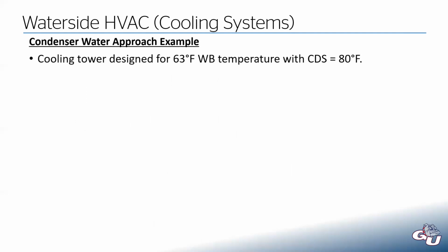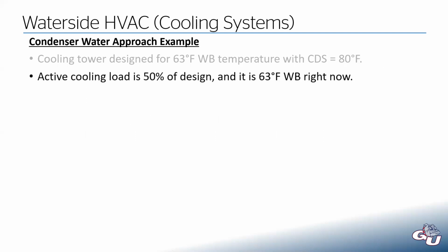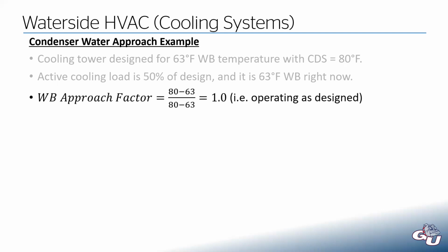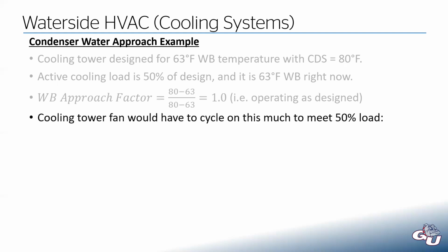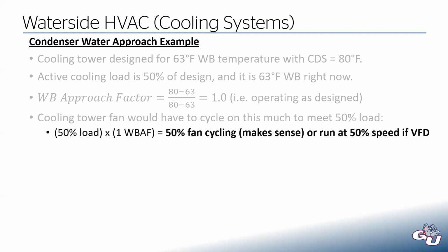Quick example. Let's say we have a cooling tower that's designed for a 63-degree wet bulb temperature with a condenser supply of 80 degrees. So that is the worst case condition. That's what we're designed for. Let's say we look at a moment in time where our cooling load is 50%. All of our chilled water systems are running at 50%, and it just so happens to be 63 degrees wet bulb right now, same as our design. Our wet bulb approach factor is going to be 1.0 because it's operating at the design temperature. So our cooling tower fan would have to cycle on 50% of the time or run at 50% fan speed because we have 50% load and we have a 1.0 wet bulb approach factor.